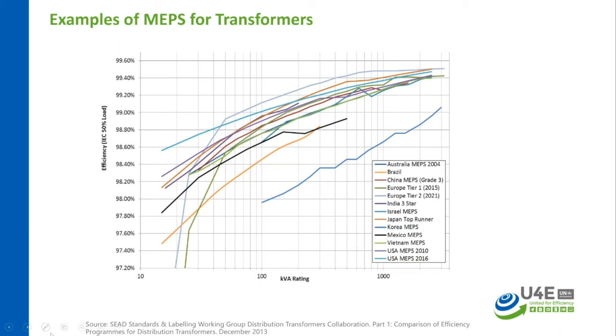You can see here that the European Tier 2 would be the best possible example, starting from 2021. This would be the efficiency standard, almost reaching 100% for the higher sizes of transformer. The most important thing to note here is that the efficiency performance of a transformer improves as the size increases, because smaller equipment cannot be made as efficient as larger equipment, due to geometric reasons. You can find that the efficiency curve with respect to different kVA ratings is not the same, which ideally it should have been.